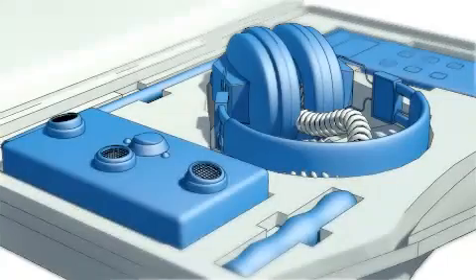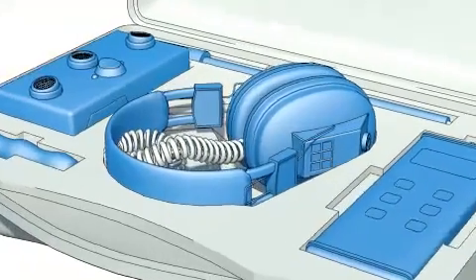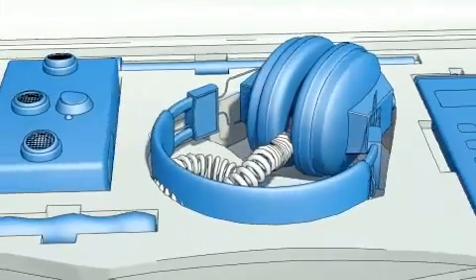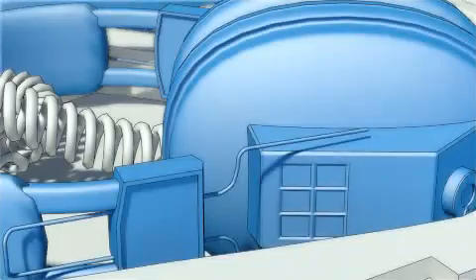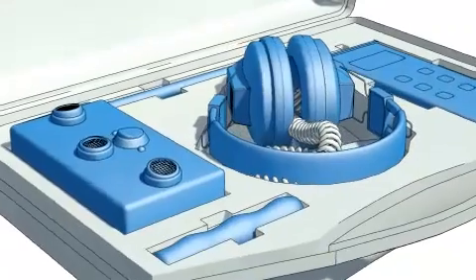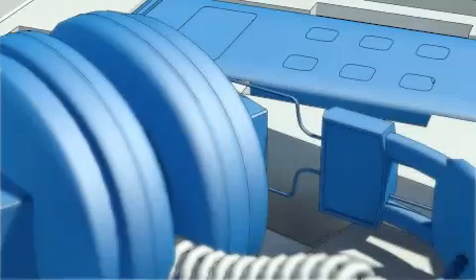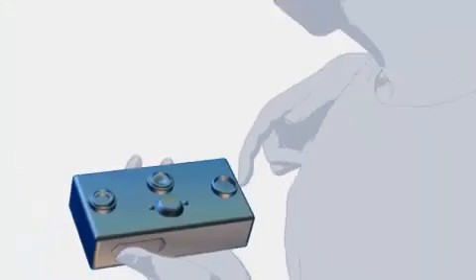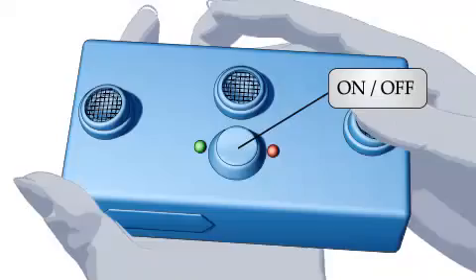A function test is required each time you use the Porter scanner. It provides you with a base number onto which you can test for leaks. To start the function test, switch on the generator. When the on-off switch is in the on position, the green LED will light. If the red LED lights, this indicates that the batteries need to be changed.